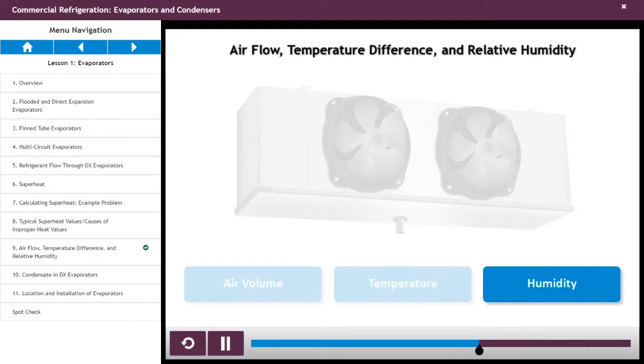A second reason the TD matters is that it affects the relative humidity. The greater the TD, the lower the RH.